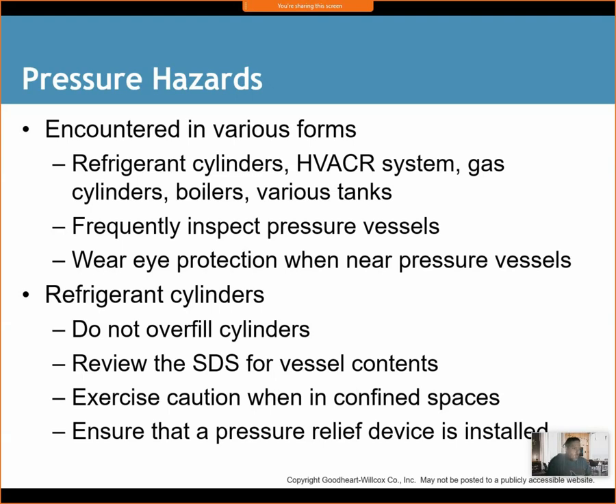I got lucky one day. I had my glasses on and was working on a system. The liquid line holds liquid refrigerant, and as I was working on the piping, closing off a valve, I had a stream of liquid refrigerant shooting towards my face. Luckily, it didn't hit me, but I can only imagine what would happen if I didn't have my glasses on. That refrigerant was in excess of negative 40 degrees. If that had happened, guess what? I would have lost my eye instantaneously. So ensure that you wear glasses at all points in time.